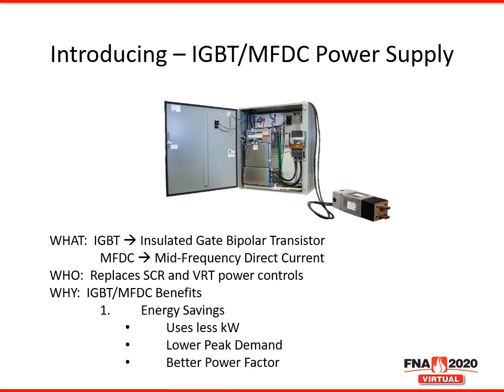In this presentation, we will be examining power characteristics of the IGBT MFDC power system. The IGBT portion stands for Insulated Gate Bipolar Transistor. This is the control portion. MFDC stands for Mid-Frequency Direct Current. This is the high current transformer portion of the power system. The IGBT MFDC power supply can be used in place of SCR and VRT power controls. Some of the benefits that IGBT MFDC offers are less kilowatt usage, lower peak demand, and better power factor when compared to other power controls.